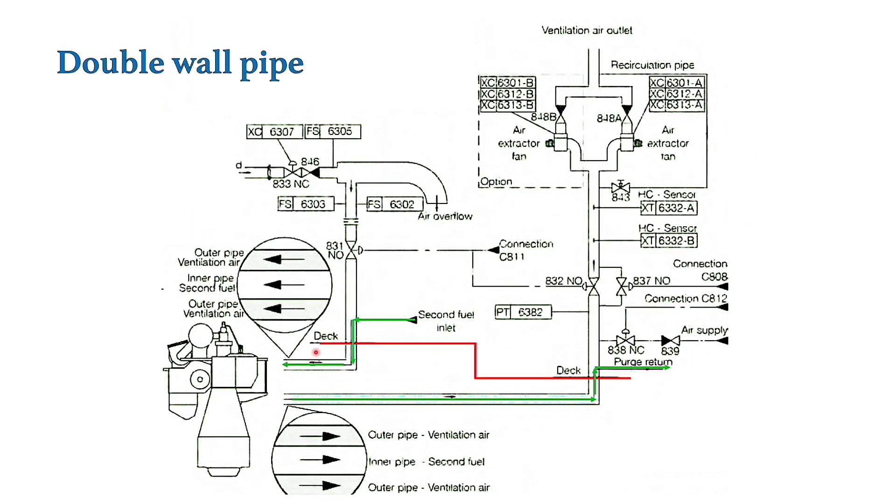As you can see on this slide, this red line basically represents the deck. So when the LPG — basically the propane — enters the engine room from the deck to the main engine, it is provided with double wall piping. This section from deck till main engine is double wall. The LPG which is returned from the main engine or recirculated back to the fuel gas supply system is also double wall. The main reason is safety — in case the inner pipe has some kind of rupture or leak, it prevents the outflow of LPG into the machinery space.